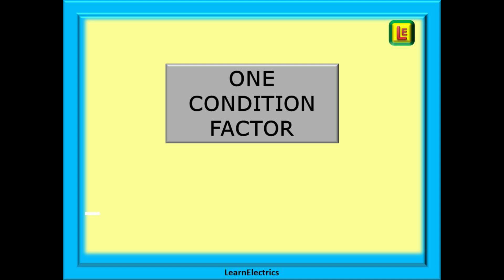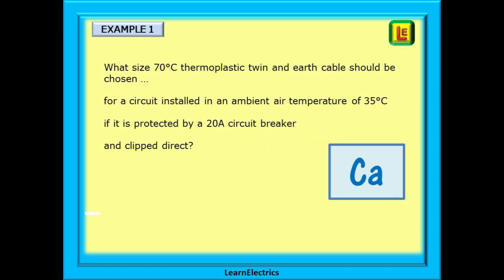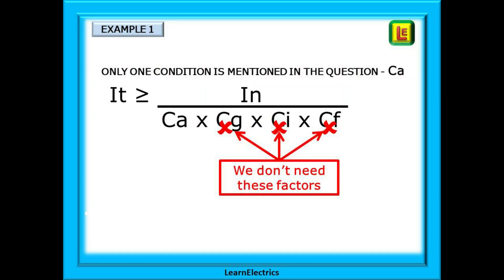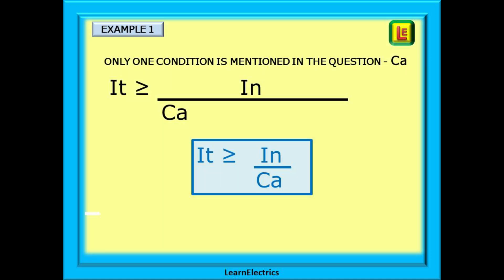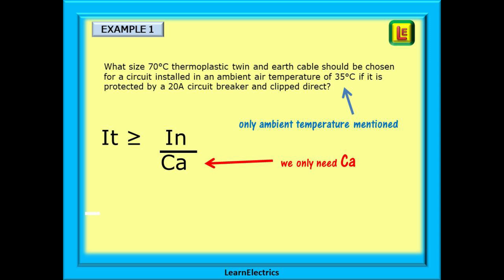Let's begin by using an example and looking at just one condition factor. What size 70 degrees centigrade thermoplastic or PVC twin and earth cable should be chosen for a circuit installed in an ambient air temperature of 35 degrees centigrade if it is protected by a 20 amp circuit breaker and clipped direct? Because it is ambient air temperature, this will be our condition code CA. If we go back to our big formula, we notice that only CA is required. Because the others are not applicable, we can effectively ignore these in the calculation. So let's get rid of CG, CI and CF. We are now left with IT must be greater than the fuse rating divided by the factor for ambient air temperature.